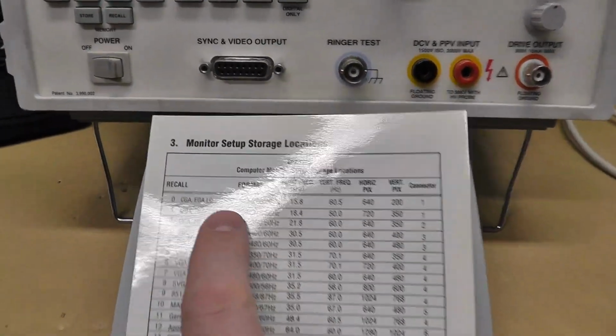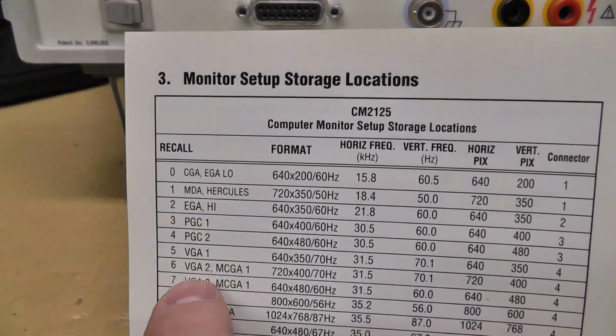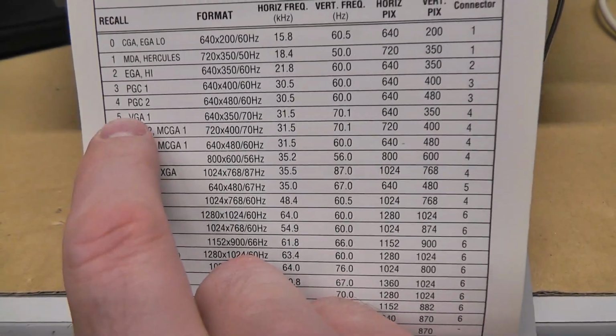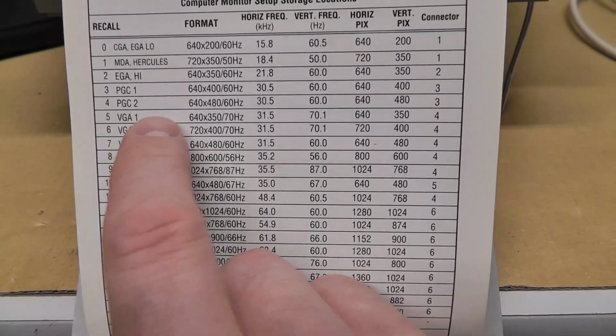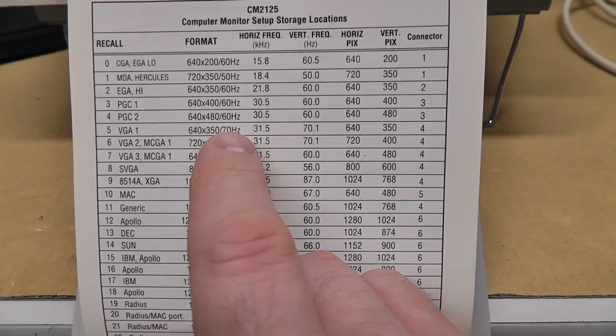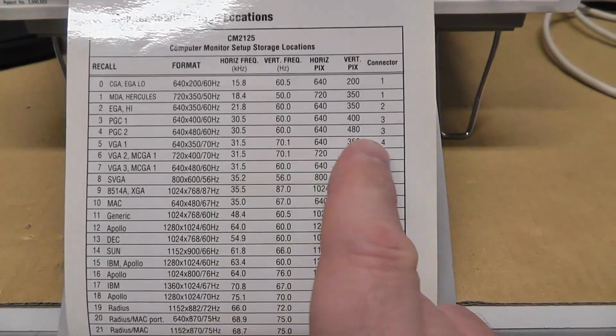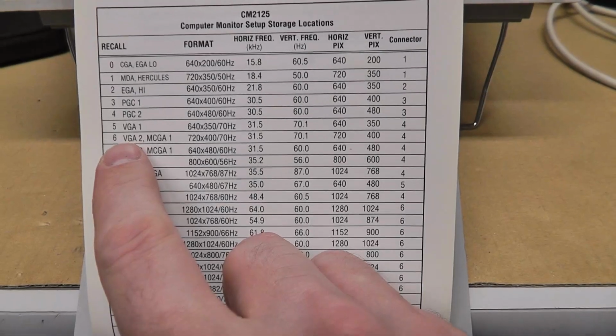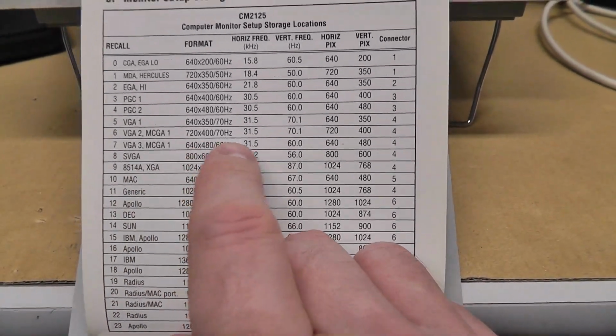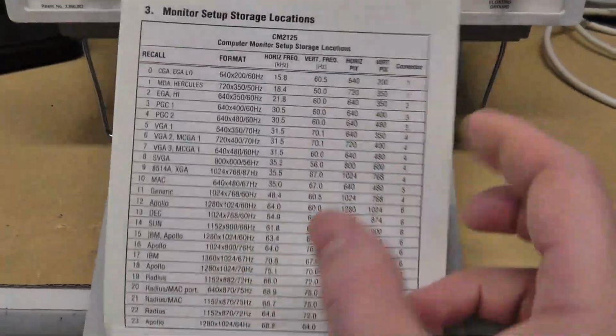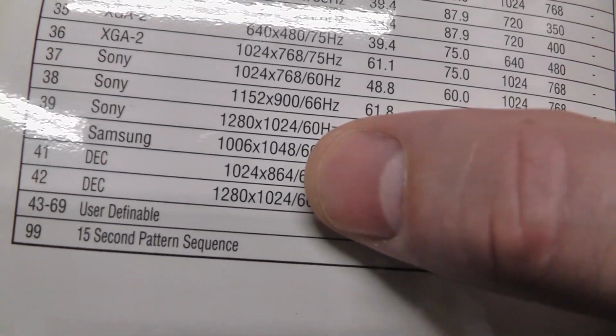Then it gives you this monitor setup information, pre-stored based off of certain kinds of monitors, like VGA 1, 640 by 350 at 70 hertz. So it's telling you what it's pre-configured as. VGA 2, VGA 3, and obviously there are something like, I don't know, 42 predefined ones, and then you can define your own between 43 and 69. I'll show you that in a second.